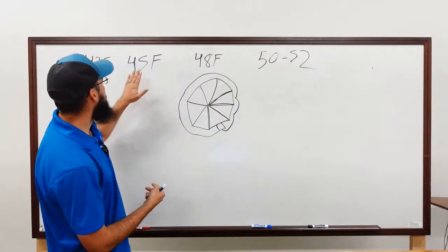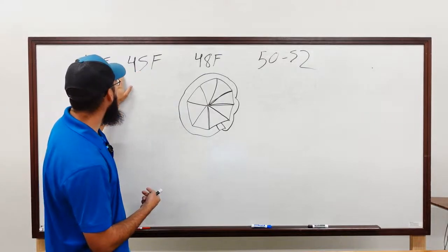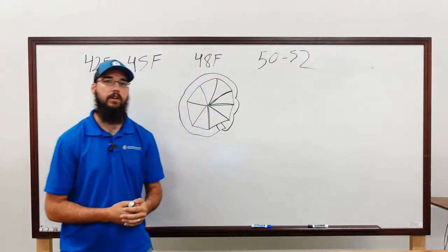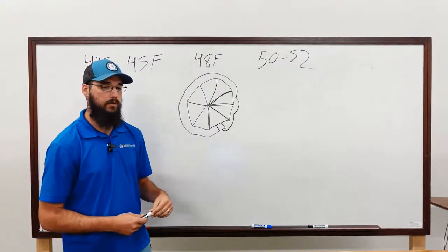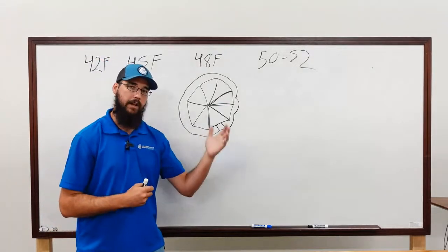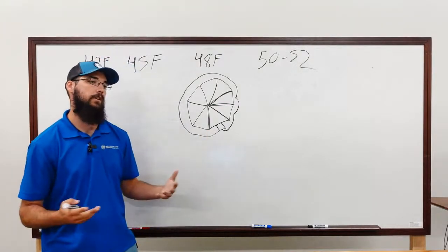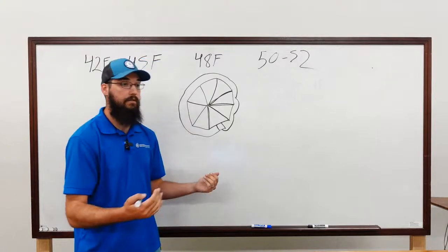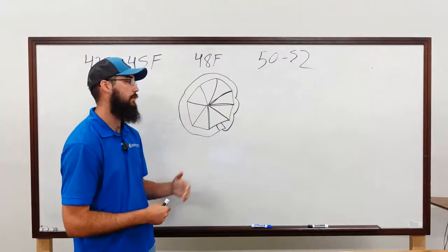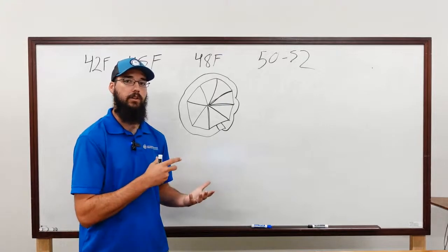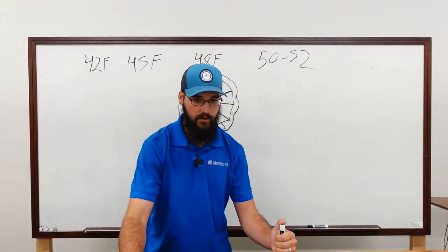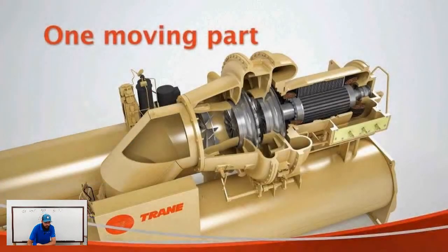So if you walk up and you see that you're running significantly below set point, you can look at the front panel on the chiller and see what IGV position am I calling for? And it may even tell you it's calling for 0%, but you can actually look at the armature, because all those things are external. So if we cycle back over, oh yeah, you can.